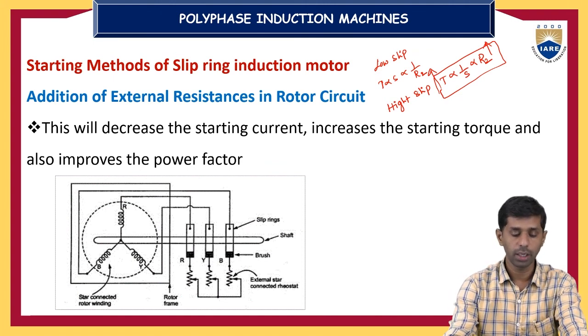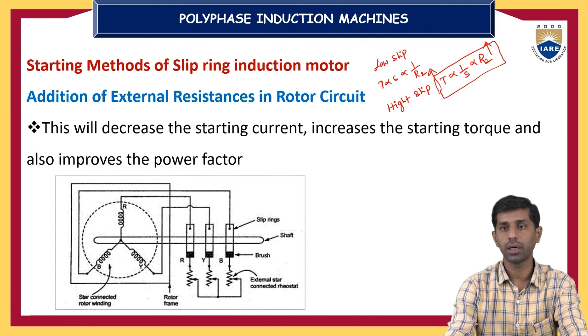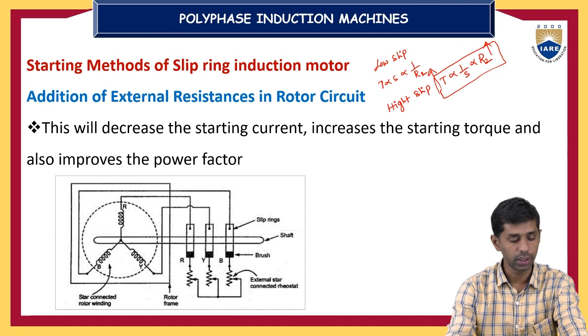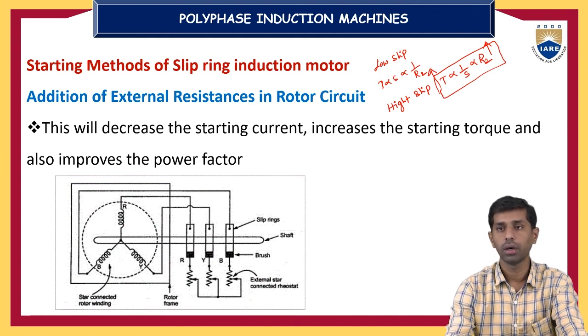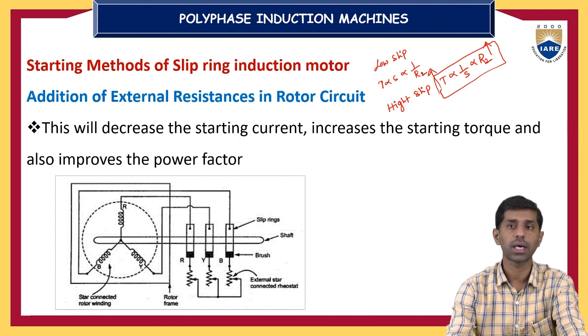So with the help of external resistors connected in series with the rotor winding, we limit the starting current into the three-phase induction motor. This is one of the beauties of the slip ring induction motor. We control the starting current as well as increase the starting torque of the induction motor only at the time of starting.